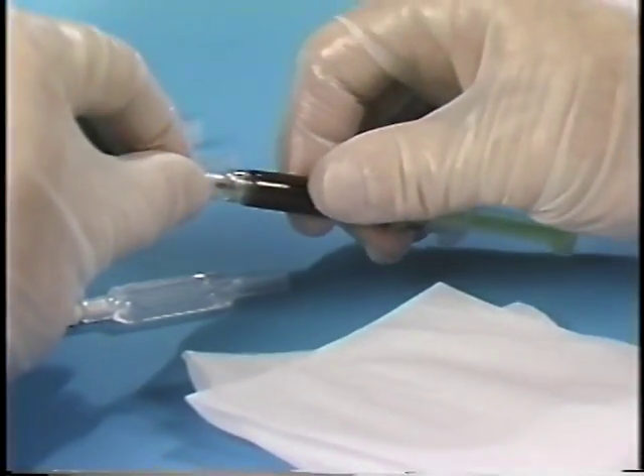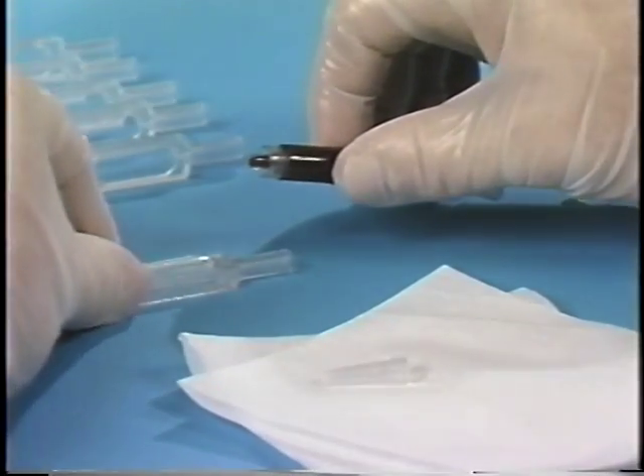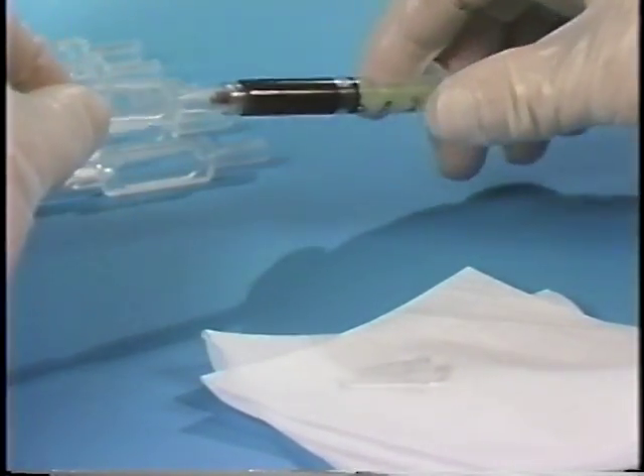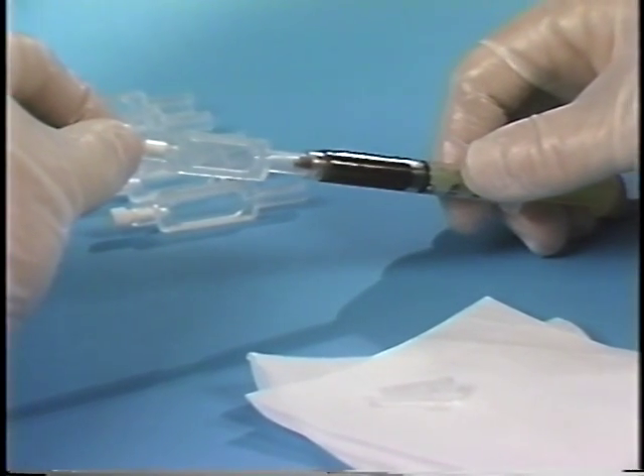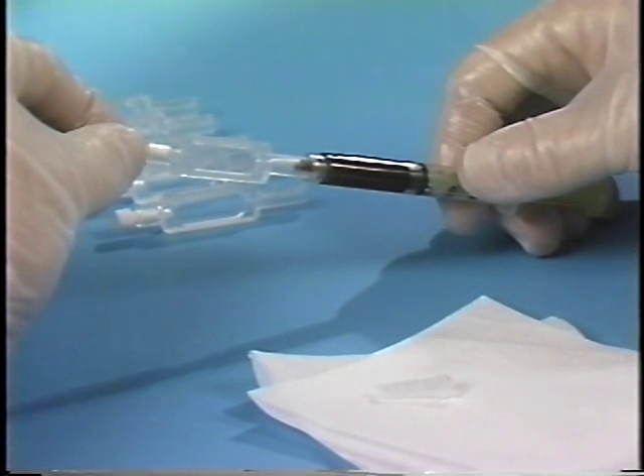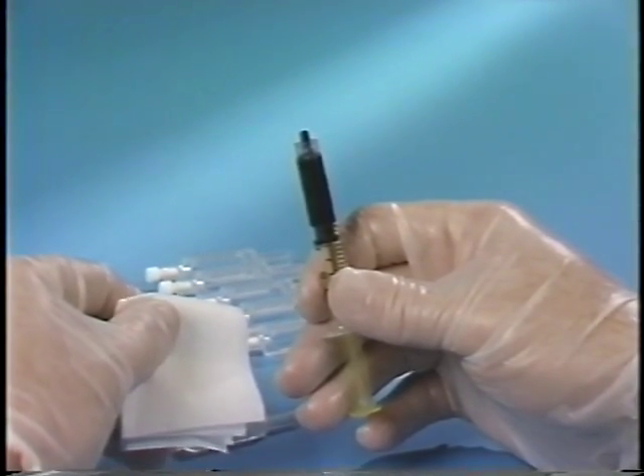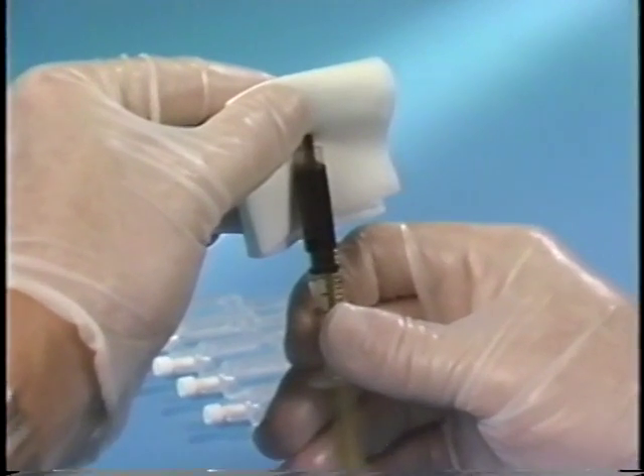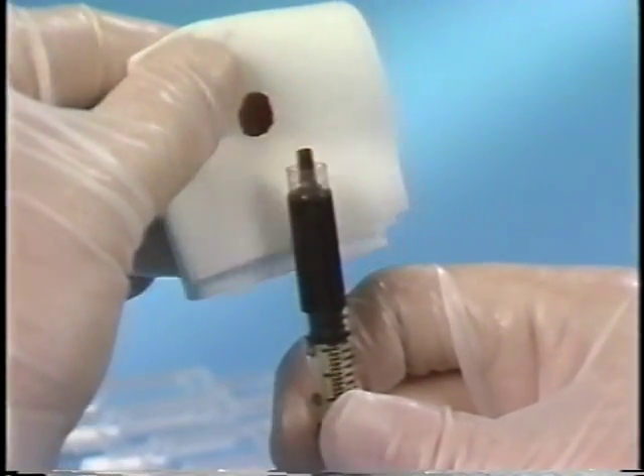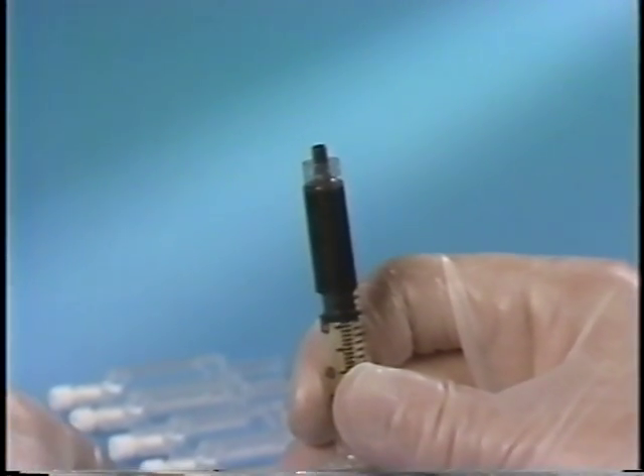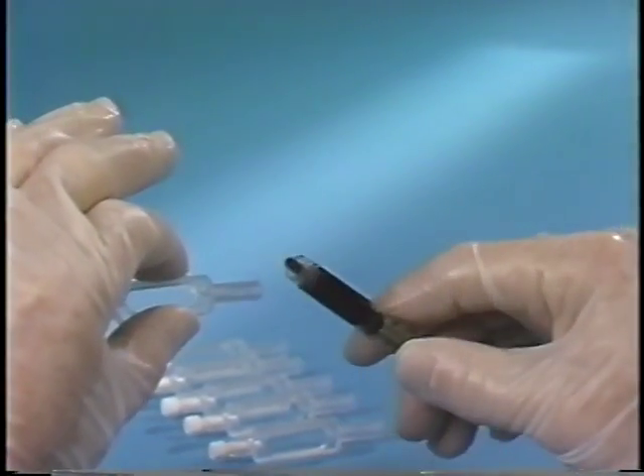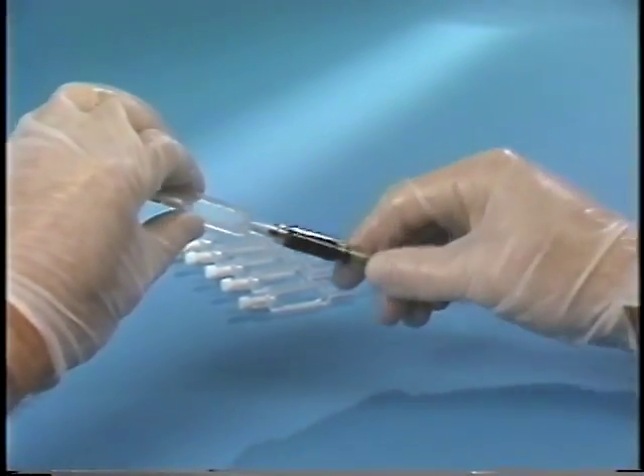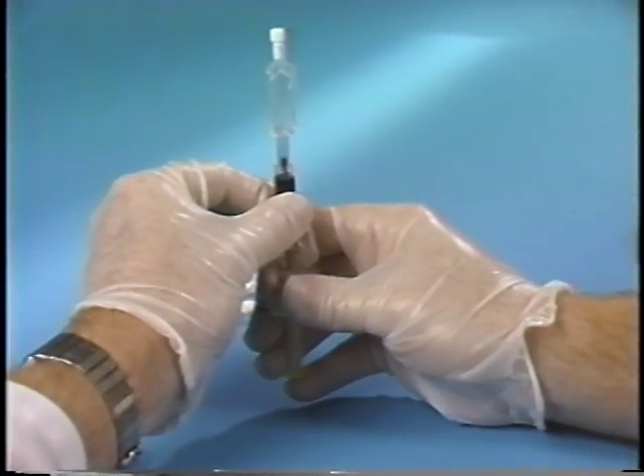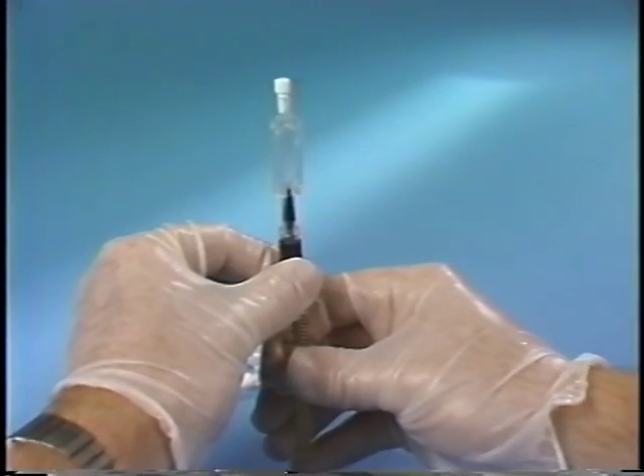The task of collecting a sample and transferring it to the cuvette requires timing and technique. A sample is drawn from a flushed line into a heparinized syringe. All samples should be analyzed within 10 minutes. All air bubbles must be expelled from the syringe prior to transferring the sample to the cuvette. To do so, hold the syringe in a vertical position with the tip up and inject a small sample of blood into a 4x4 or tissue. Then place the cuvette over the syringe tip, twist and secure in the vertical position. Slowly inject the blood into the cuvette while tapping the syringe body to expel any air bubbles.